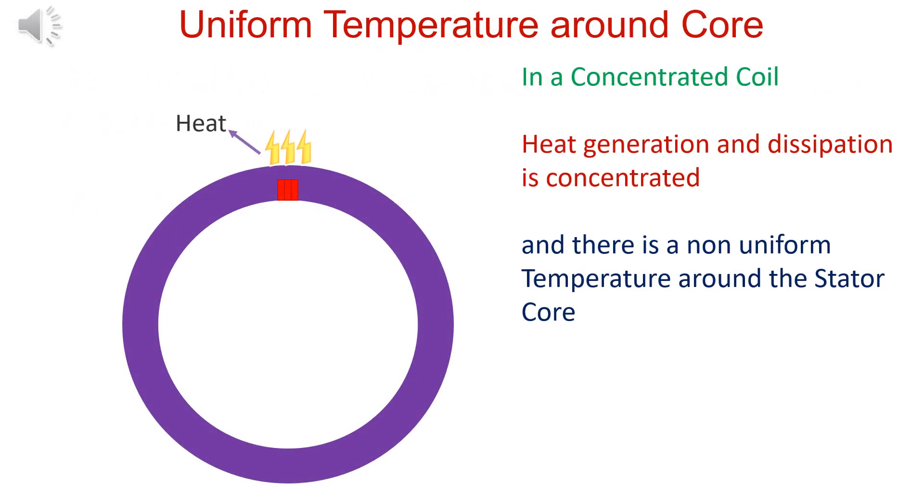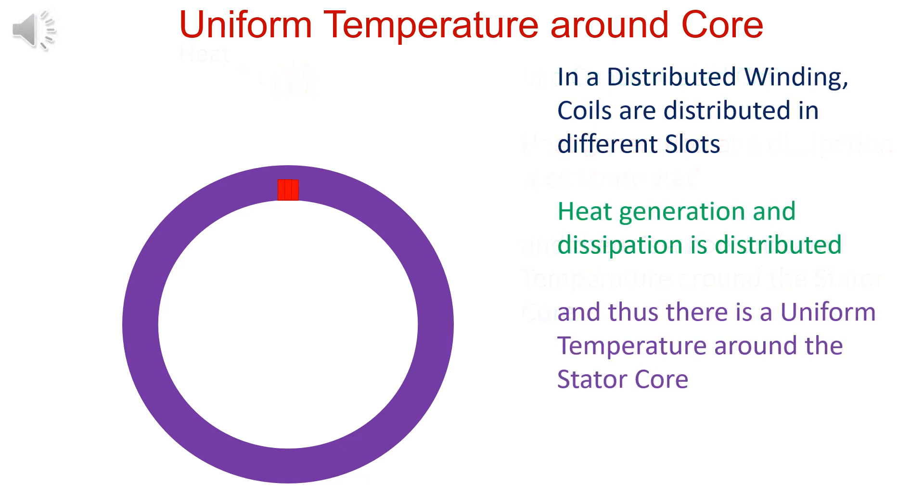In a concentrated winding, generation of heat is concentrated. This leads to non-uniform temperature around the stator core and thus the stator core is not fully utilized. In a distributed winding, heat generation is distributed and temperature is uniform around the core.